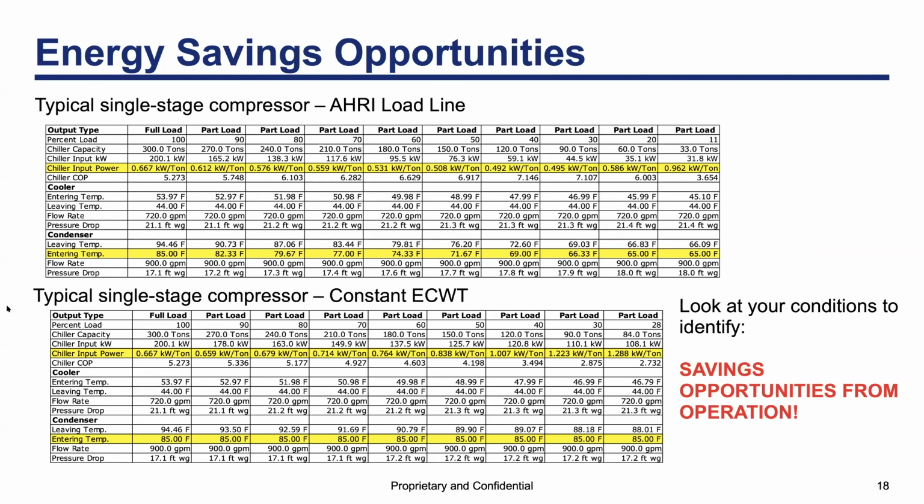And of course, we all know that throughout the year, a chiller operates at different capacity points, which basically indicates a load profile. So the system efficiency, or SPLV, in this case will be the weighted average of these conditions. At the end of the day, you will have to customize your own values for a better calculation for your specific systems or application. But I wanted to give you a general example.